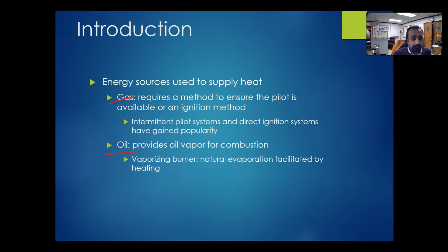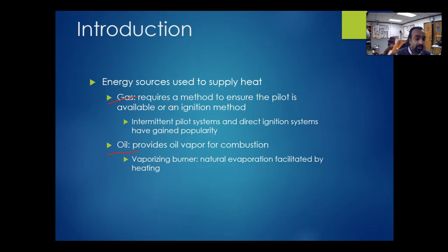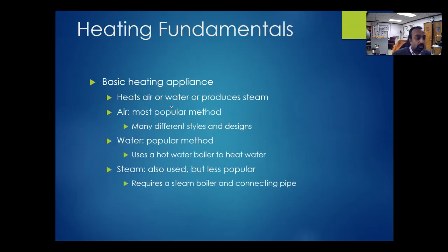Thinking about electrical control, you need to prove the flame. Whenever you have gas, it takes a little more time to ignite, so you need to prove the flame very quickly. The time between dispensing gas and lighting it should be as short as possible, because if you're smelling gas every time you turn the burner on, something is wrong. With oil, everything is completely contained and the oil is introduced along with its required combustion air.